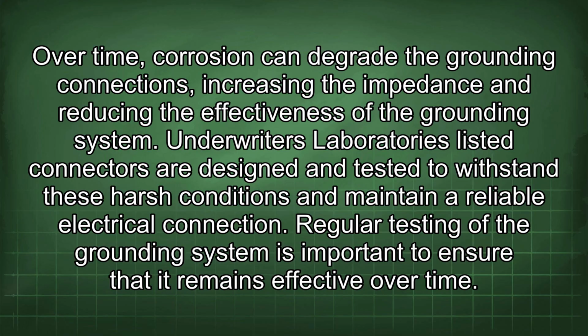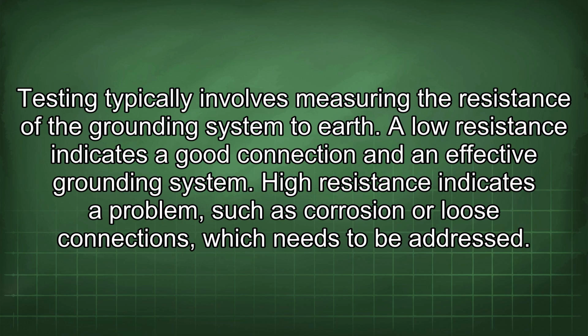Regular testing of the grounding system is important to ensure that it remains effective over time. Testing typically involves measuring the resistance of the grounding system to earth. A low resistance indicates a good connection and an effective grounding system. Higher resistance indicates a problem, such as corrosion or loose connections, which needs to be addressed.